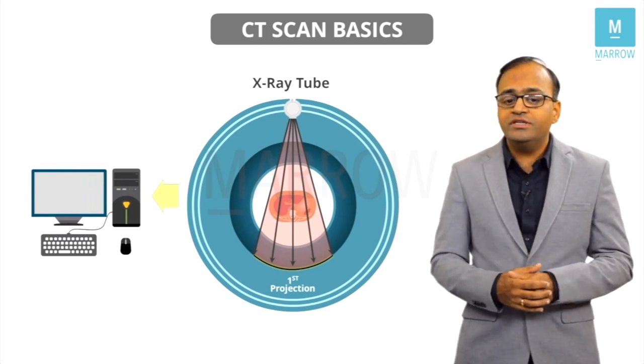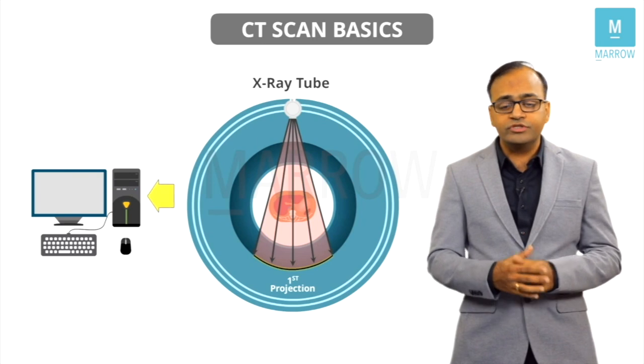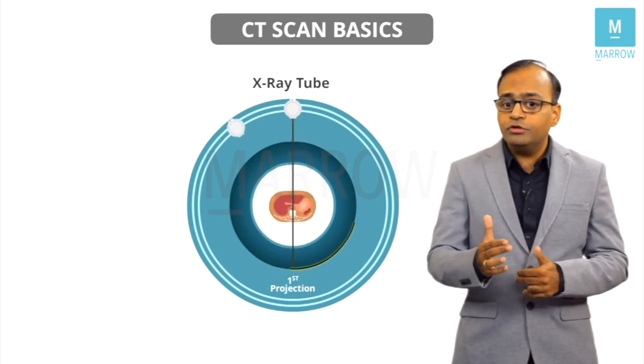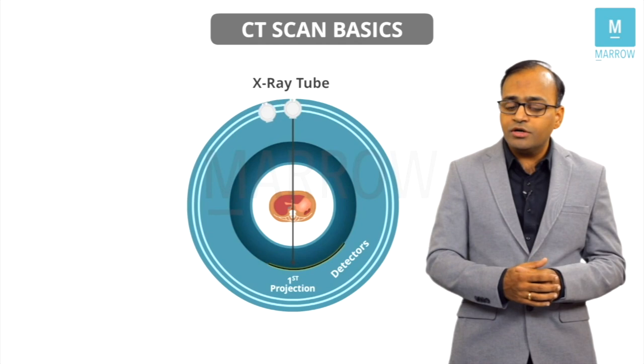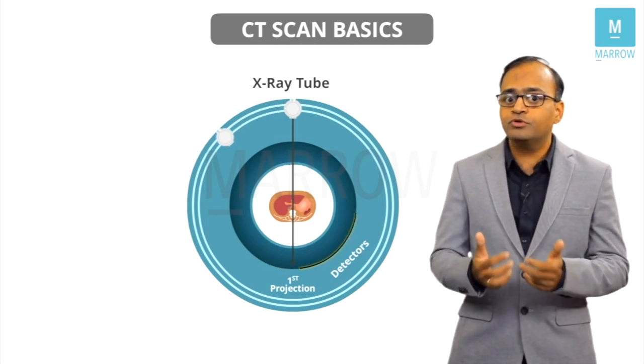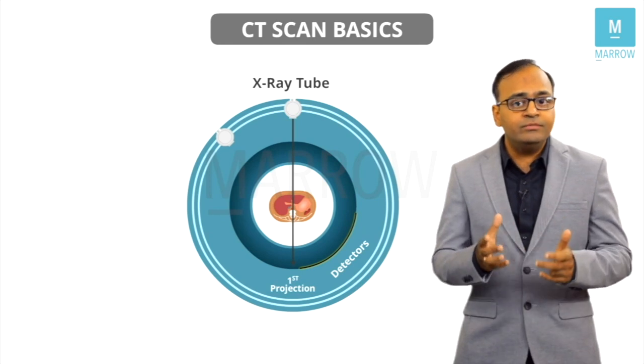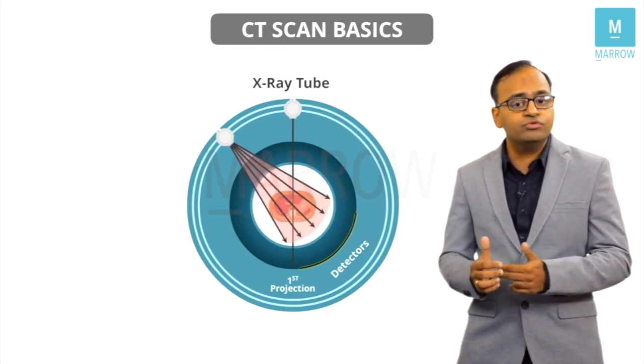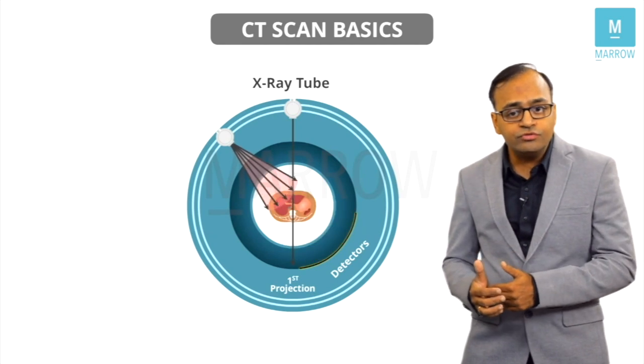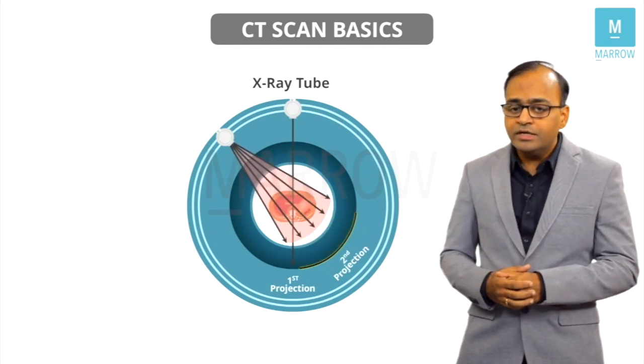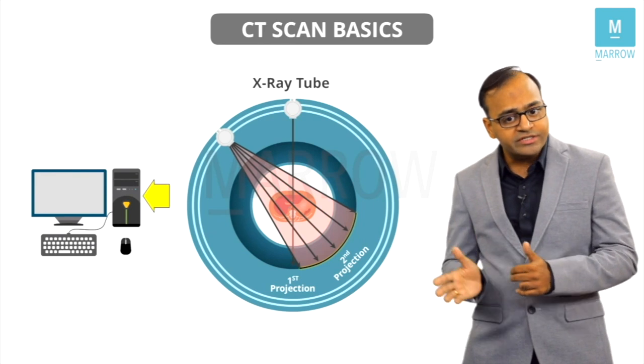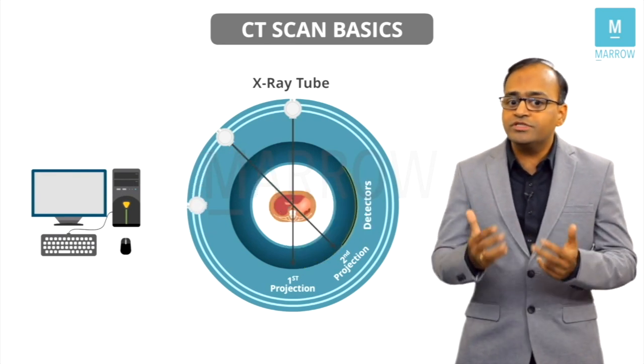Now, the next step that occurs is very beautiful. The x-ray tube is moved to a new position along the circumference, and the detectors are also moved. From this new position, the same process is repeated — the x-ray beam is produced, this beam passes through the patient's body, and we get another image. This is called the second projection, which looks different from the first projection. Data is again transferred to the computer.